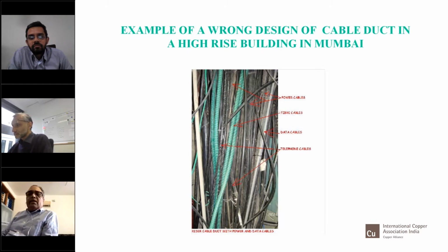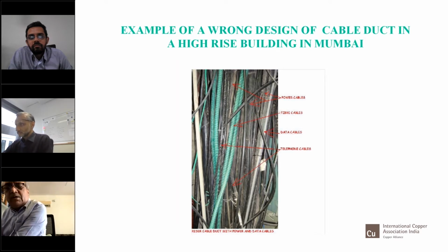This ultimately gives rise to problems. About 10 years ago I was called on this assignment and shown this. When the door was opened, I could not stand in front of that duct because the heat emanating from the cables was so high that I had to step back two steps before speaking to the gentleman. So these are the kinds of things that can happen in badly designed buildings.